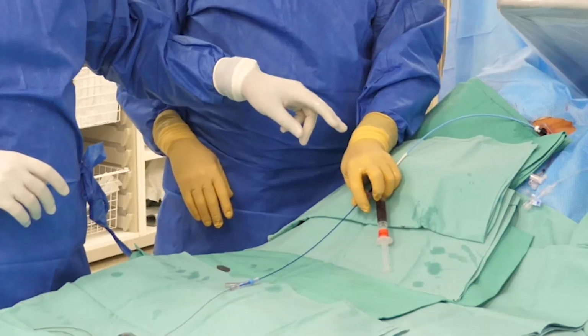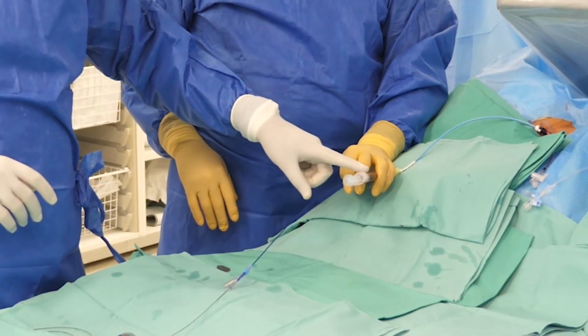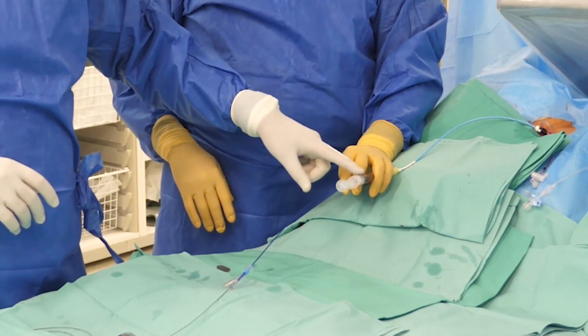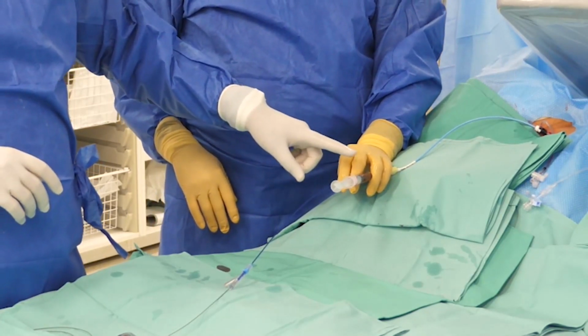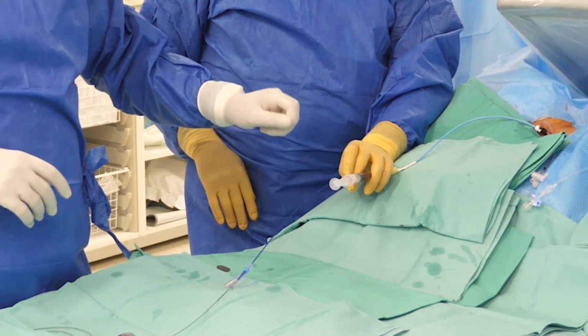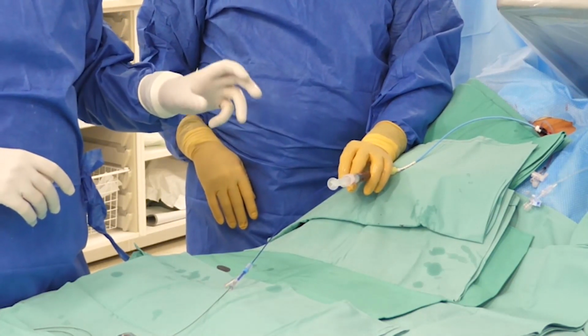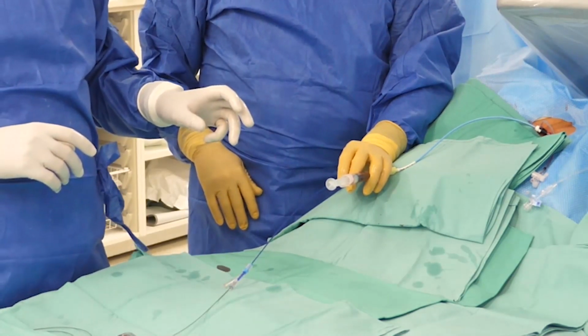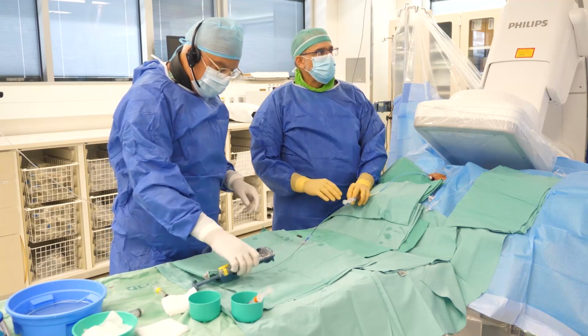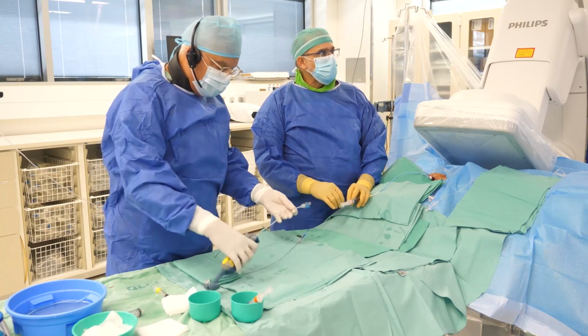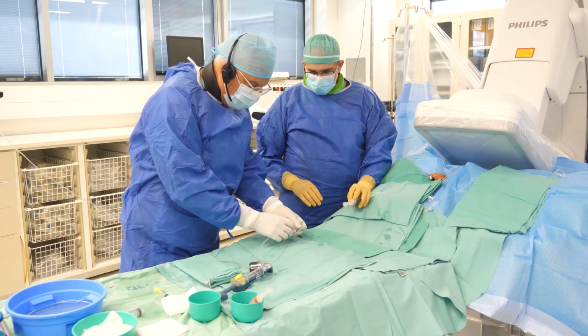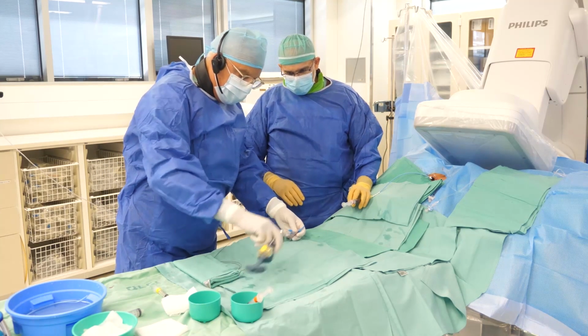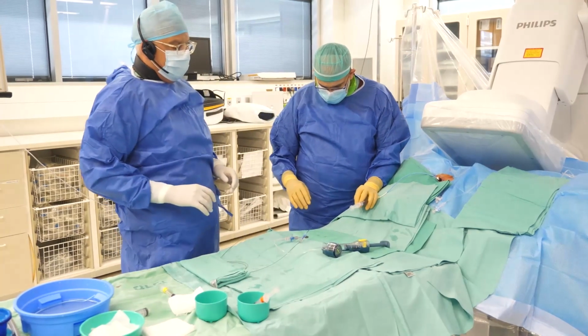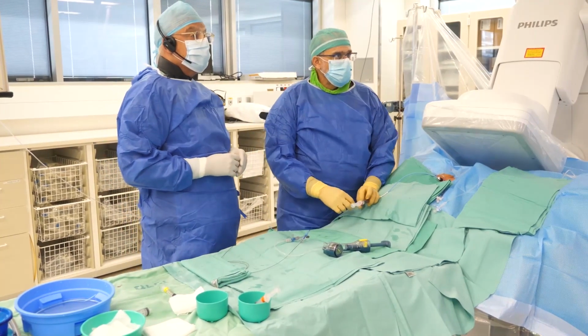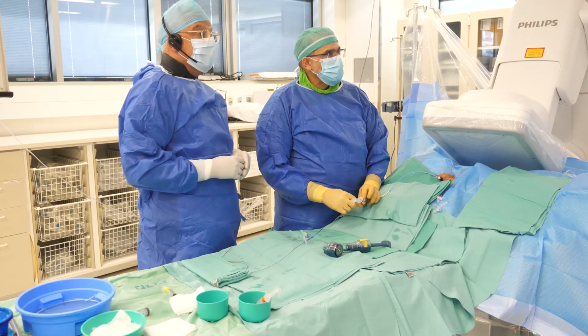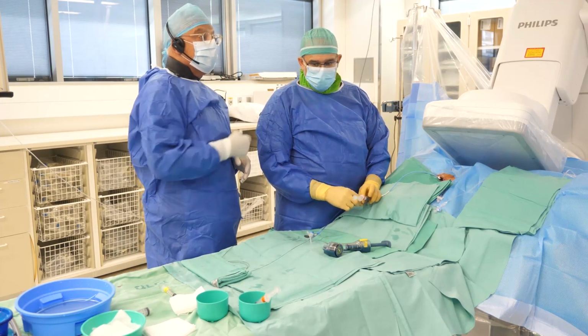so we can continue. We have a Luer-Lok syringe with contrast at the end of the Y connector, at the end of the guiding catheter. We will take an injection of contrast into the coronary sinus when the balloon is fully inflated, just to make sure that we are properly oversizing. What Sami will do now is take the reducer to the site of implantation. I'm connecting the indeflator. We're not doing a negative on the indeflator. And Sami will advance the reducer to the site of implantation, which is up to the tip of the guiding catheter. One shot, go in.